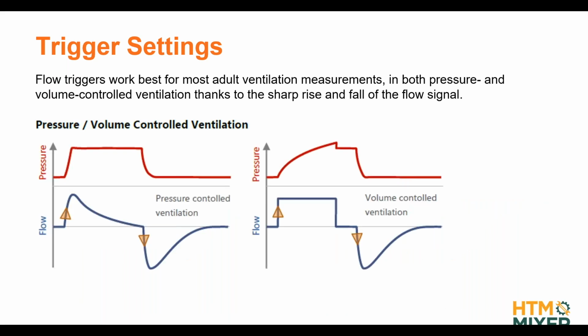typically when you have gas flow measurement and you test a ventilator, you have flow and pressure waveforms that look somehow like this. On the left-hand side, we have typical waveforms for pressure-controlled ventilation, where the ventilator is controlling the pressure in inspiratory time. And on the right-hand side, volume-controlled ventilation. The nice thing is that in both cases you typically have these very steep falling and rising edges of your flow signal. The other nice thing is that your zero baseline of flow is usually zero. So at the beginning of your inspiratory phase, you have a rapidly rising flow in positive direction, and at the beginning of the exhalation phase, it crosses the zero line and goes negative, right?